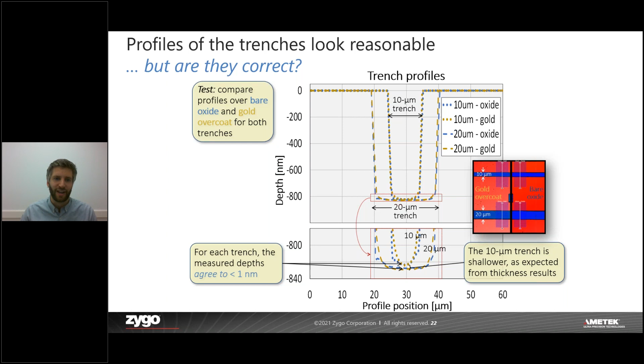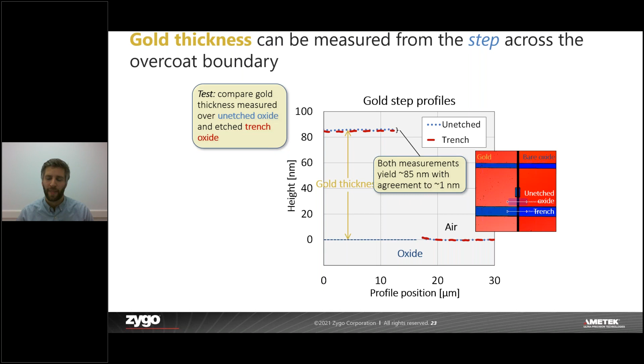And indeed, if we measure from the gold area to the uncoated area, we see that same less than 1 nanometer agreement in measuring the thickness of the gold. And so we can be pretty confident that our technique is self-consistent and it produces reliable results. So this model-based technique will measure individual layers of thin film down to about 50 nanometers in ideal conditions. And like I mentioned, it's available for both the NewView and the NexView NX2 platform. And that's available now. So that resolves the issue of thin films, at least in a very large way.